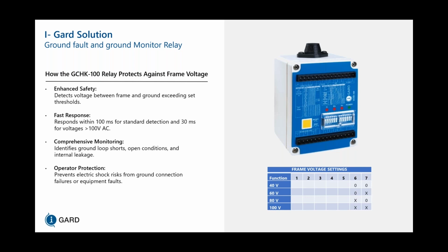based on non-fail-safe and fail-safe modes, ground fault pickup levels, and various other different features that you can utilize, including ground fault delay and ground check features. So it can detect voltage between frame and ground exceeding set thresholds up to 100 volts. It responds within 100 milliseconds for standard detection and 30 milliseconds for voltages greater than 100 volts AC. It gives comprehensive monitoring to identify ground loop shorts, open conditions, and internal leakage coming from ground fault. And it also provides operator protection to prevent electrical shock risks from ground connection failures or equipment faults.